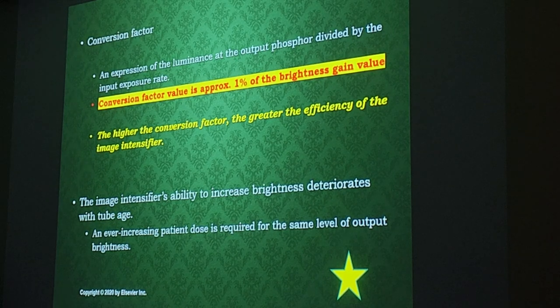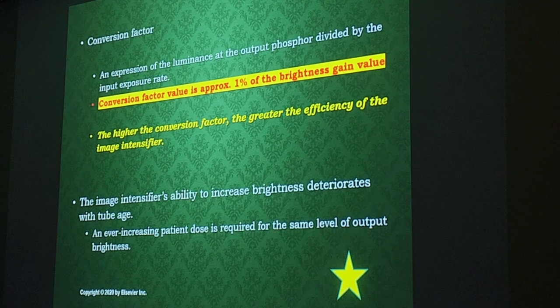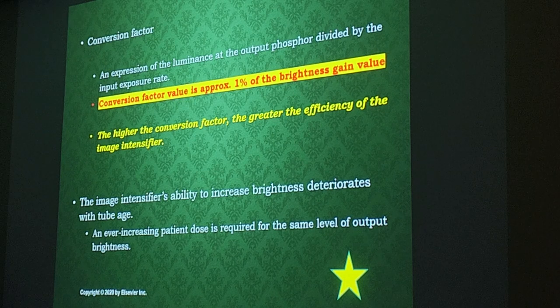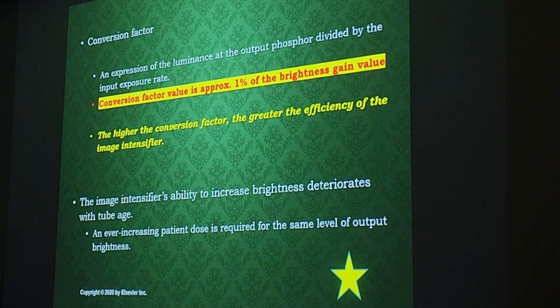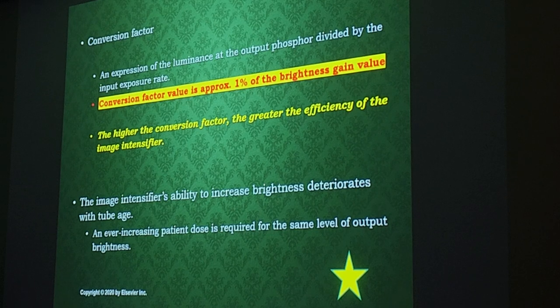Typically when you do the conversion factor formula, the answer you get is approximately going to be one percent of your brightness gain value. So if you do a problem using the brightness gain and then do a problem using conversion factor, your conversion factor answer will be one percent of your brightness gain answer — because the division is inverted: input divided by output versus output divided by input.